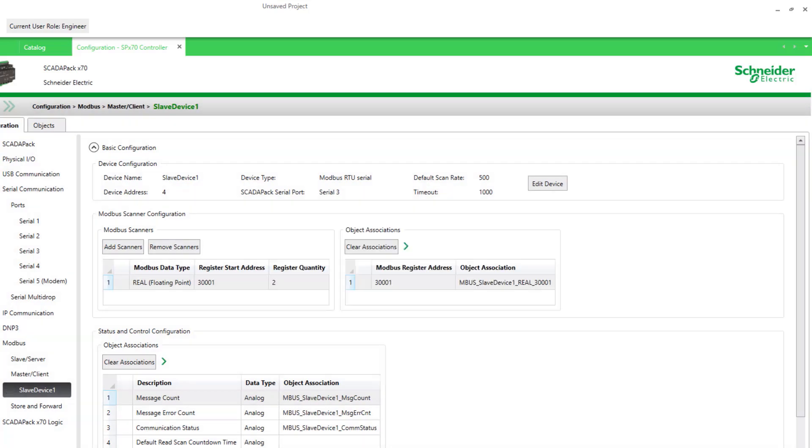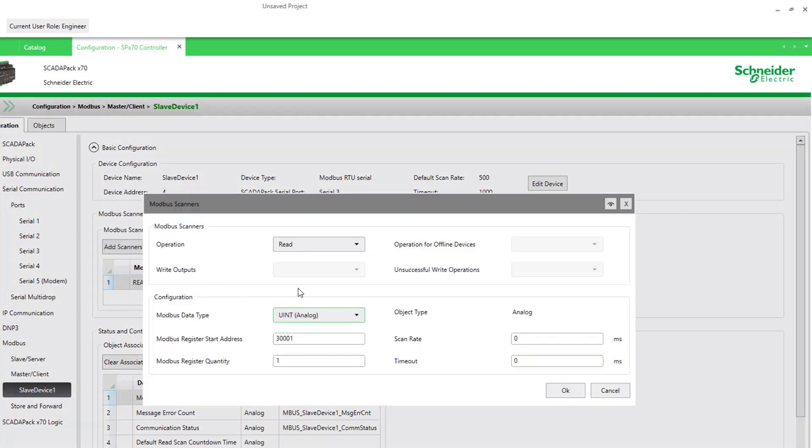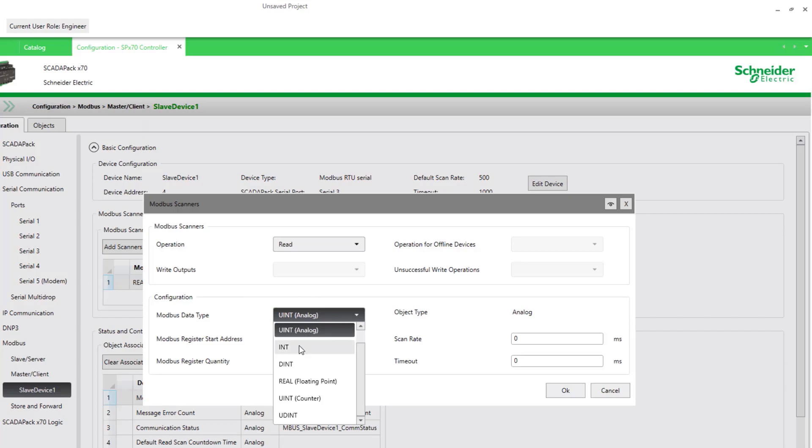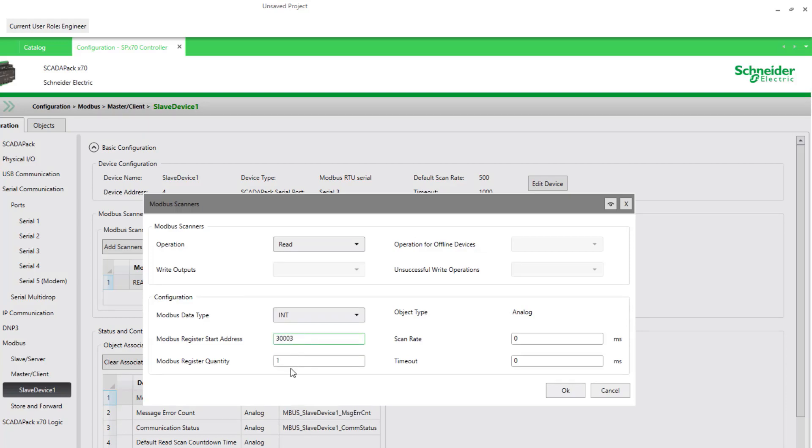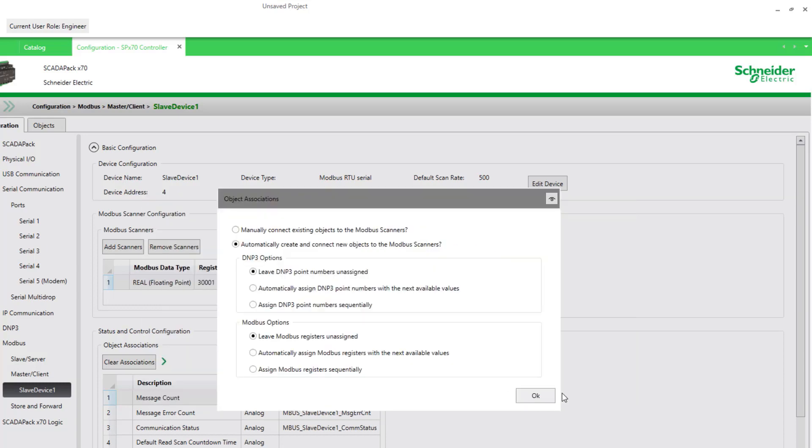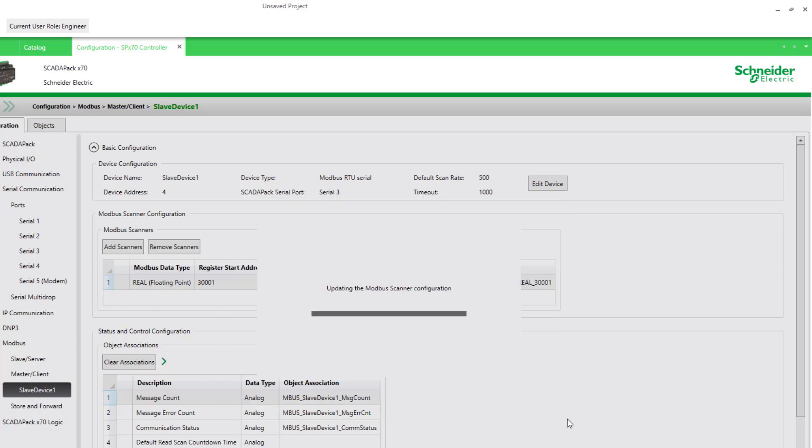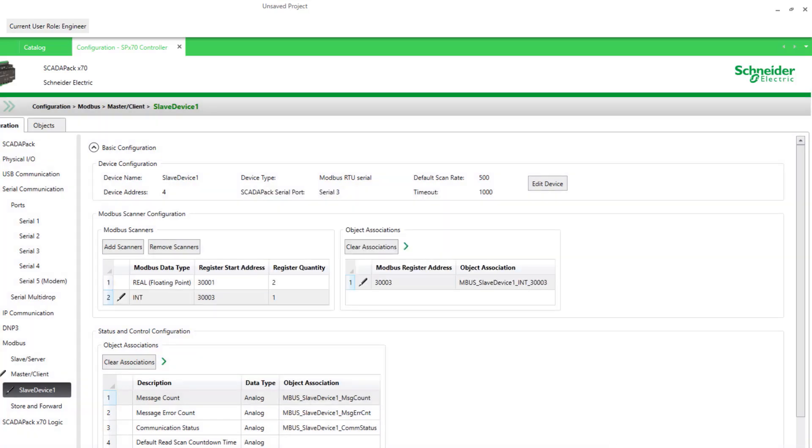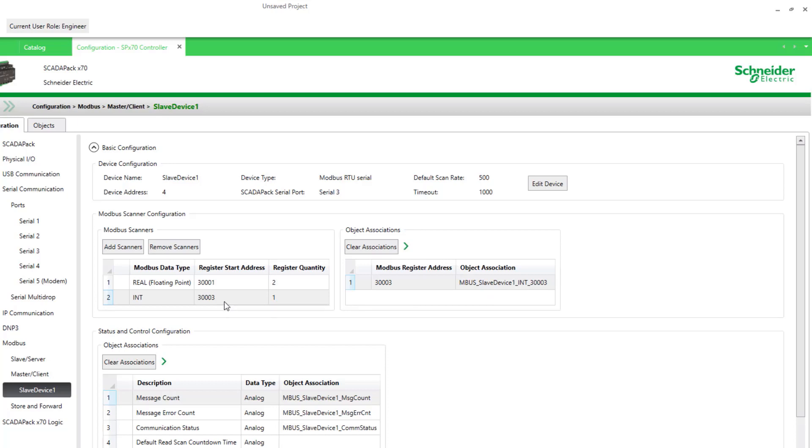Here is what we do when we assign to objects. We're going to create new objects and not assign any addresses to those objects at the moment. So this is the default. I'm going to apply that. I want to add one more scanner to pull my temperature, which is an integer. So I'll make it a signed integer. And it begins at 30,003. Just the one register there. Here we have on the right now telling you which objects were created for each of the registers being pulled. This is the long name for our temperature value at register 30,003. And this is the one for the first one for pressure.